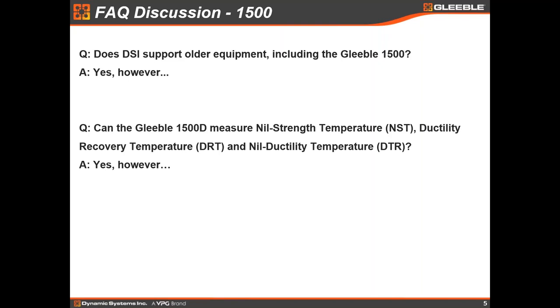Can the 1500D measure nil strength temperature (NST), or DRT and DTR? Yes, it can. However, you will need some apparatus or equipment that probably came with the machine when you originally purchased it. So if you're still running a 1500, chances are you're taking very good care of it and you probably still have that equipment handy. If you don't, reach out to Jake. We probably can't sell a new apparatus, but the machine is capable of doing that.